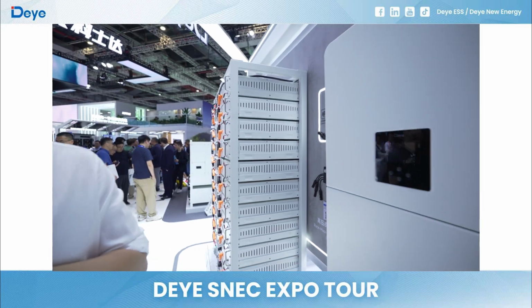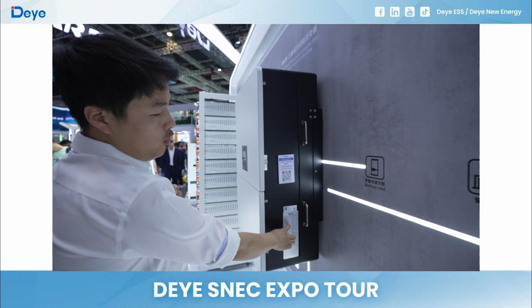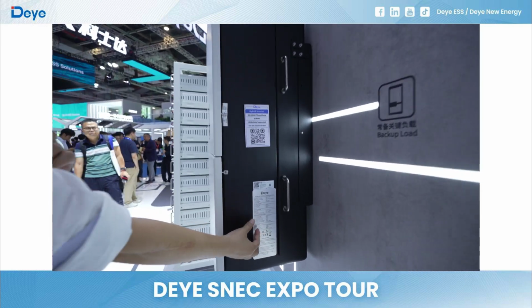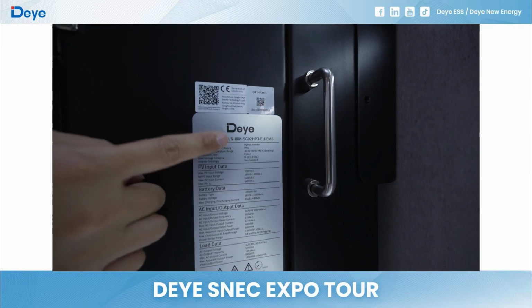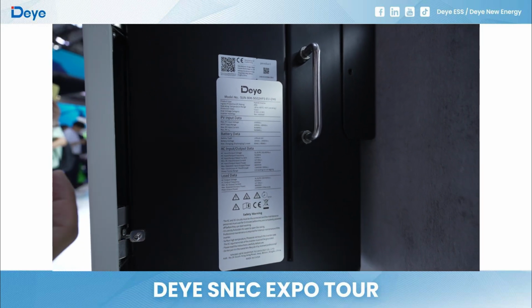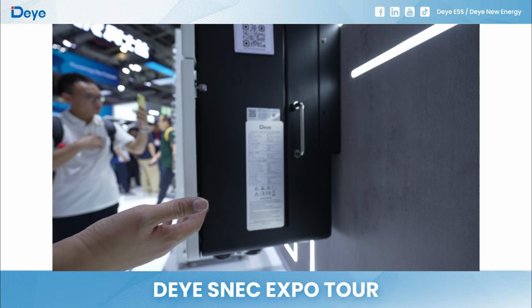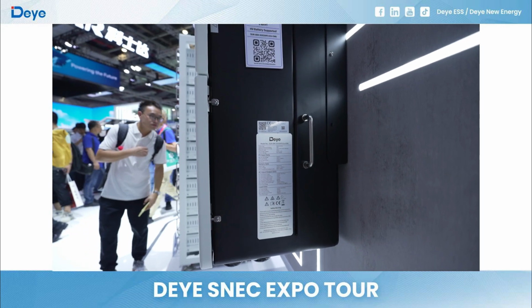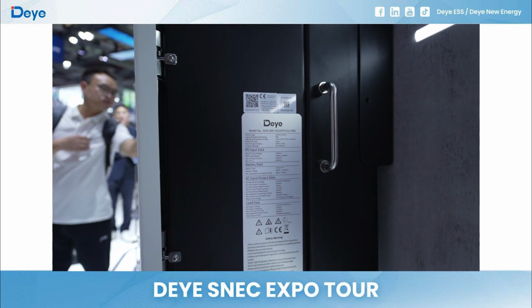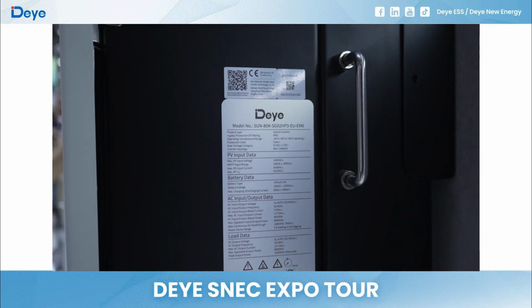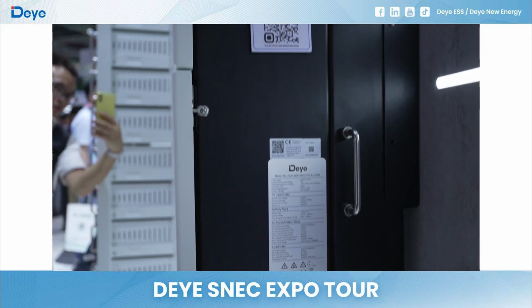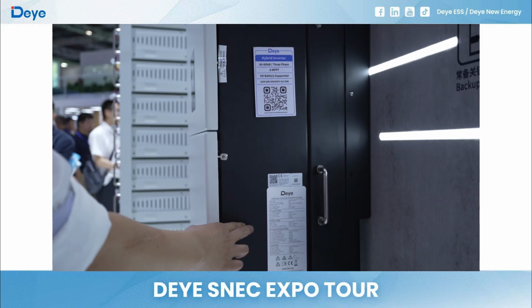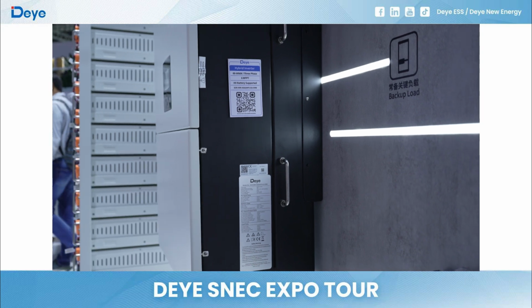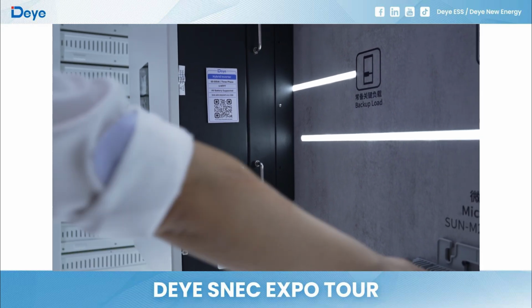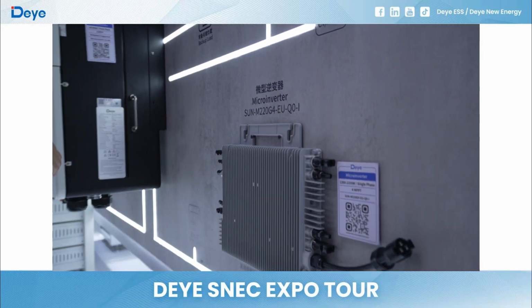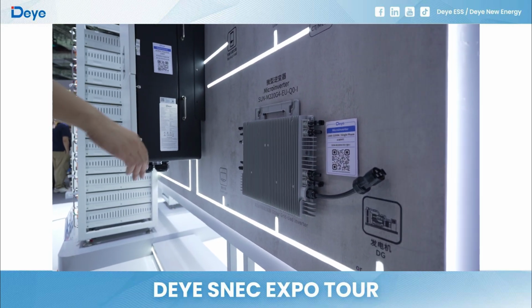Okay, let's come here. This is the main parameters for the hybrid inverter. Let's see it clearly. This is the 80 kilowatt 3-phase hybrid inverter. It has 2 independent battery DC-DC circuits, and each battery DC-DC circuit current is 80 amps. So in total, the battery charge and discharge current is 160 amps. The maximum PV input voltage is 1000 volts. The battery voltage also is 1000 volts. And we install a microinverter here. This is the AC coupled system, AC coupled on the generator port.